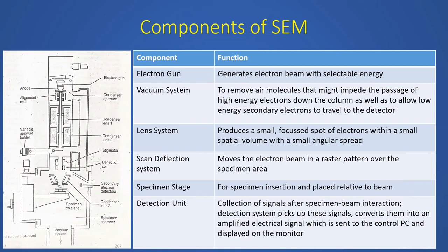Most biological specimens you need to work at very low kVs, right? To get the proper information. Because as you go to higher and higher kVs, the electrons are much more energized. These are very highly energetic electrons and they'll penetrate the specimen. That is not something you want in an SEM. It could be bad. So typically it is restricted to around 30 kilovolts.